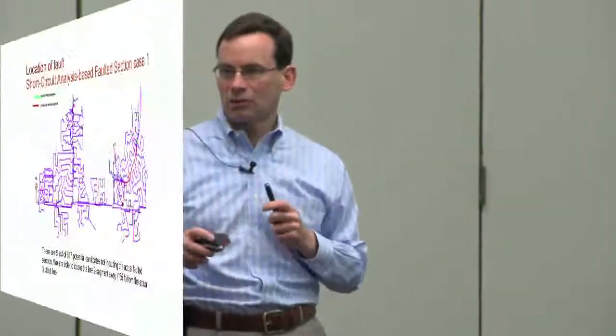These are permanent ones, and so the SAIDI clock runs. So we can actually give them that fault segment that can help them reduce the bifurcation steps and find that place. And really what I learned, I always thought they were replacing them, but they're actually isolating just to get service back, and then they'll come back later and replace the cable or whatever they find. And that's why I know it was mostly cable failures, not so much. But there were definitely some termination issues, like in the switch cabinet.